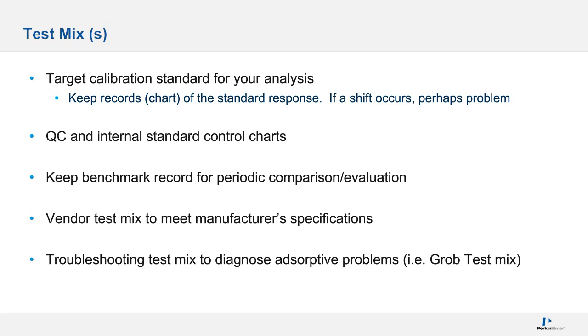Vendors also have test mix, and with these test mix, we try to make a test mix that's testing the instrument and not something else that may be going on. So they're very selective, the compounds that we use to test the instruments. For instance, when we test repeatability for the liquid autosampler, because we want to investigate the liquid autosampler, we're not checking for activity in the liner, so we use a very inert compound. So we get a true test of that liquid autosampler. So they're very specific. And then there's some commercially available test mix, and the Grob test mix is one that I'd like to discuss now.